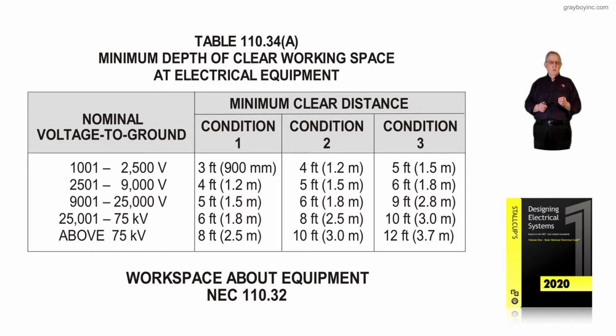Just a note to the user of the NEC, high voltage is addressed in most every case in the last part of an article, like 240, 250, and so forth. It's the last part of the article. Now, notice this workspace about equipment rated over 1,000 volts is the same. The minimum clearance distance is based upon condition 1, 2, or 3.